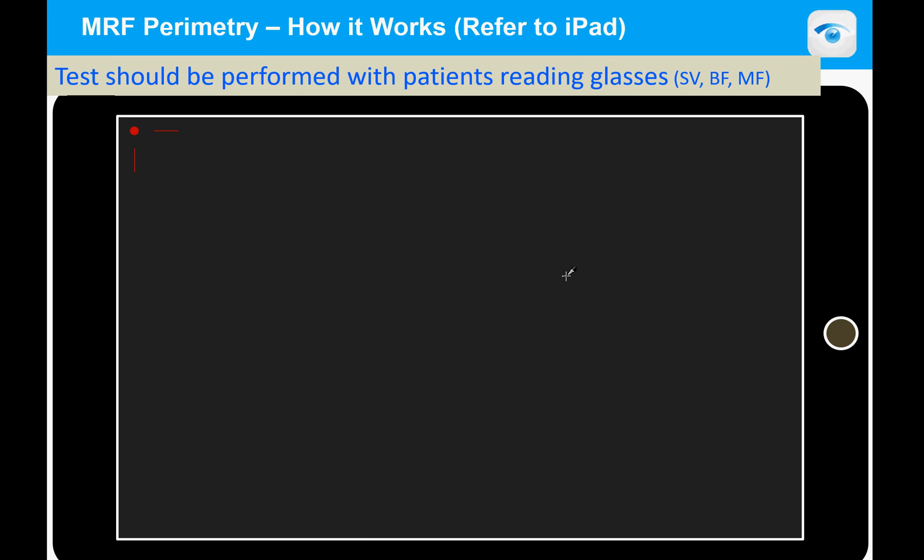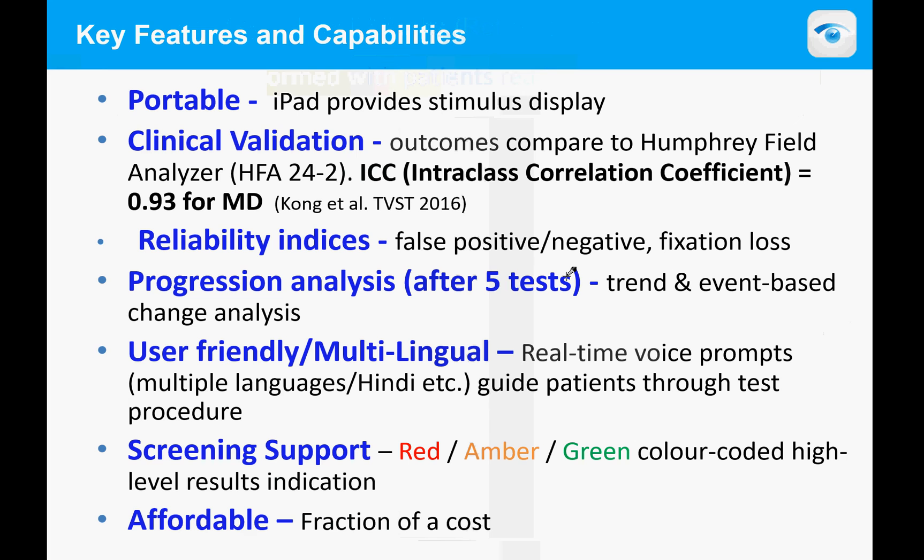For a patient to do this, they need to wear their normal reading glasses in either single vision, bifocal, or multifocal formats — it doesn't affect the test outcomes. The test is portable, the iPad provides the stimulus display, and it has been clinically validated. The intraclass correlation coefficient is 0.93 against the Humphrey. It has reliability indices, progression analysis, and supports 14 languages including Hindi.